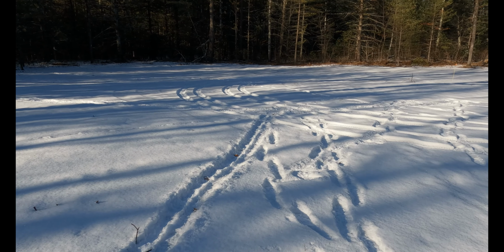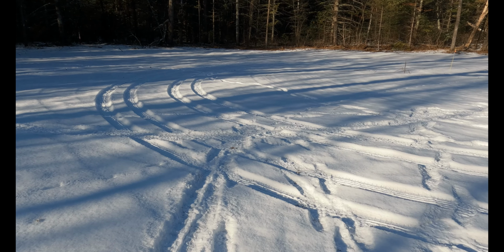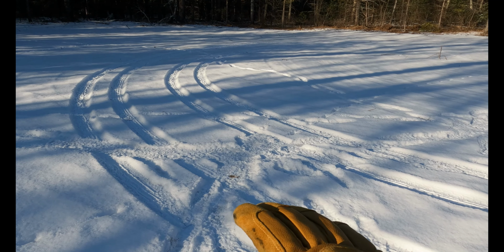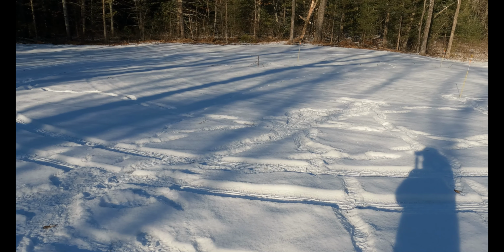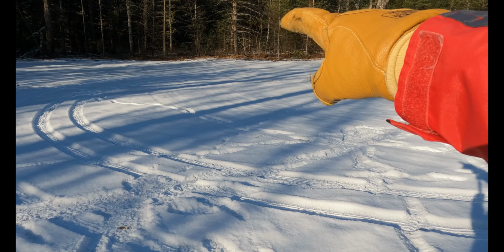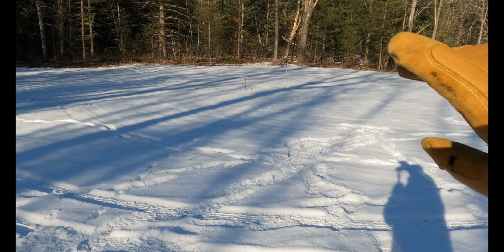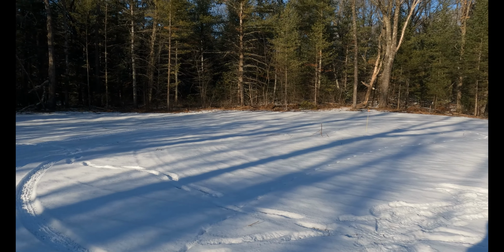So yeah, if we could get a meter pedestal in here, that way if it's standing close to the building, maybe you could tie it into the building, but in the meantime we could take the service out of there and then run it over to that corner of the house. They would probably set a transformer, I'm assuming, somewhere over there by the woods, and then run the single phase primary down, and then do a single phase riser pole or whatever.